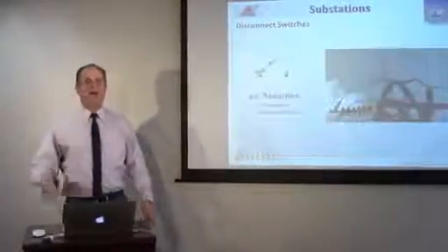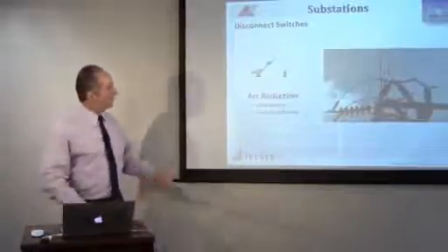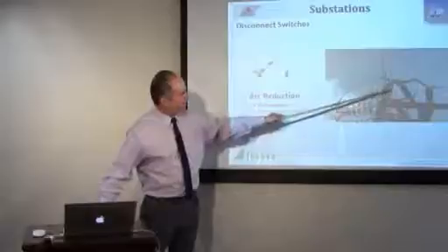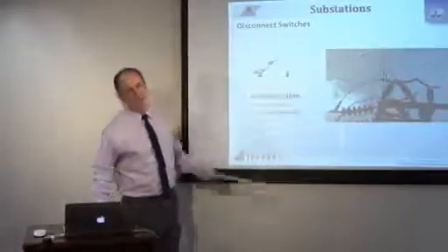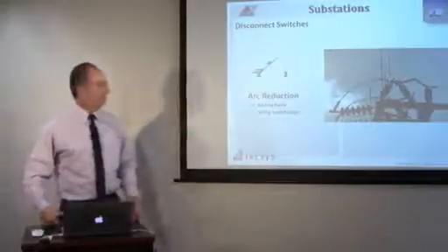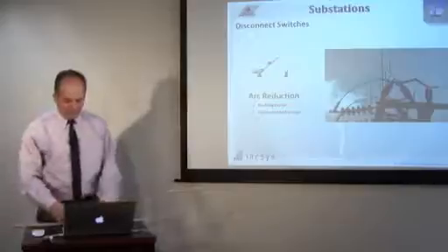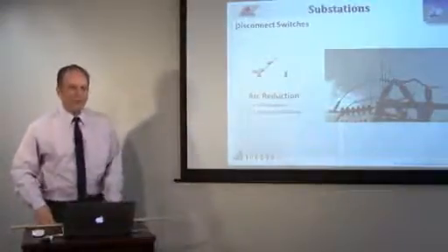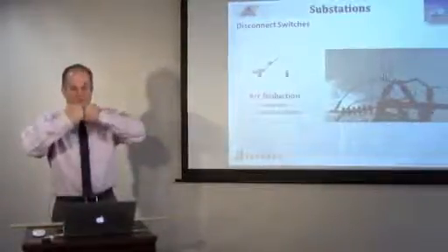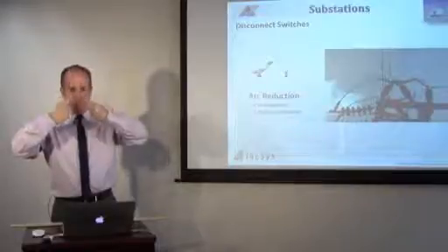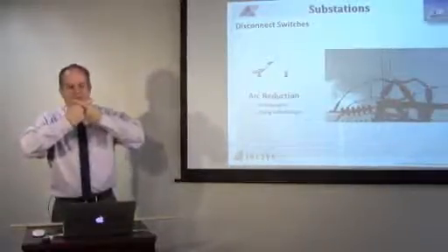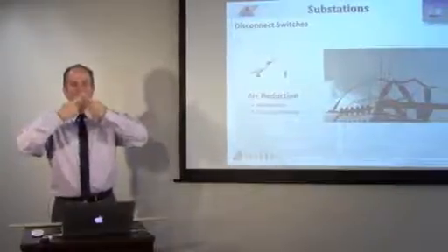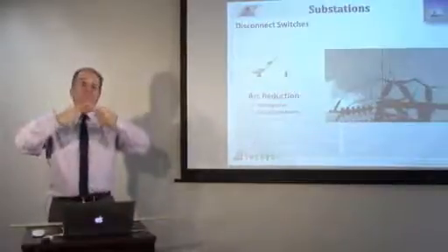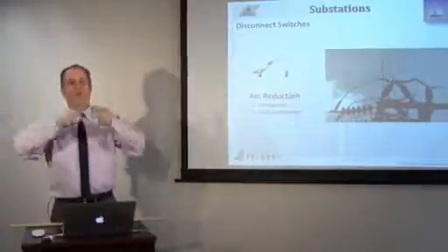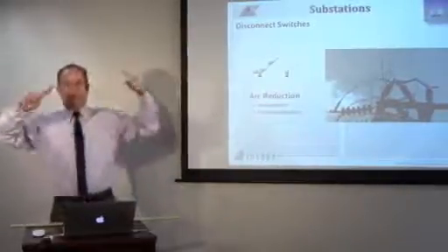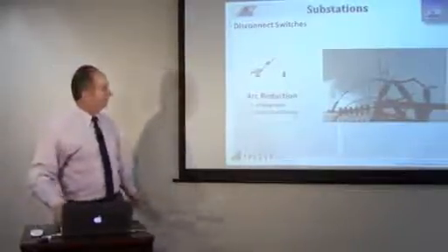Okay, now we're going to talk a little bit about disconnect switches. Disconnect switches are air brake, they're visible switches. A lot of them have these whipping horns or arcing horns and whips. And the idea there is when you're trying to open up a circuit and there's a little bit of load or line charging or something on there, when you open it up, there's going to be an arc. But if you have these little whips or arcing horns, what happens is the main contact's open. Now you have high resistance steel, increasing the resistance, reducing the current flow, reducing the arc, and then finally it just kind of breaks apart because they're spring loaded. Some of those longer ones have a pretty good whipping action to help extinguish the arc.